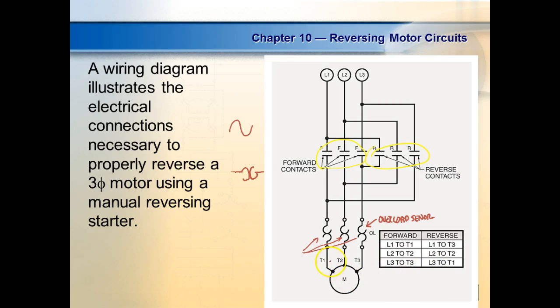And of course, these are our connections, L1, L2, L3, but it doesn't show how. Notice when it comes into the motor it's labeled T1, T2, T3, and the bottom of our power relay is labeled what? T1, T2, T3. So it's straightforward as long as we're not reversing. But what we've got to do is come up with some way to only reverse what? 1 and 3.